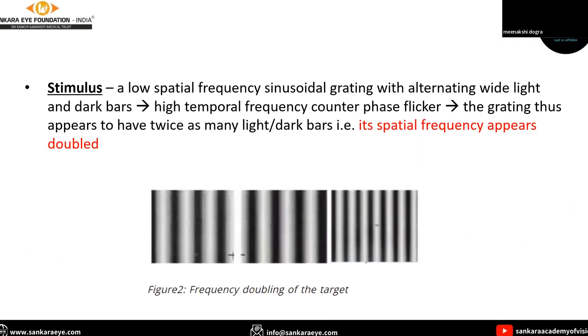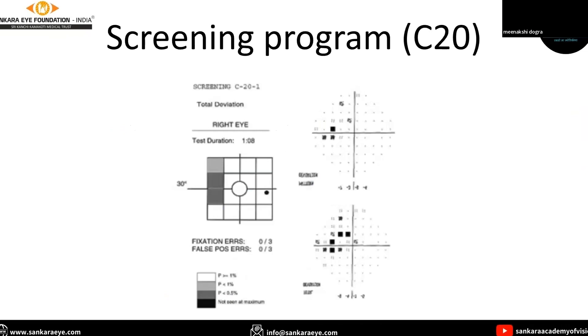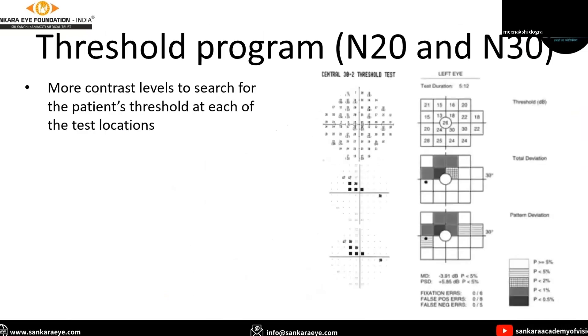The stimulus is a low spatial frequency sinusoidal grating with alternating light and dark parts which undergo high temporal frequency counter-phase flicker. The patient fixates on a black dot at the center of the screen and presses a button whenever the grating is seen. Based on the contrast required to perceive the grating, a threshold is estimated at the tested location. It offers a screening program C20 and threshold programs N20 and N30.